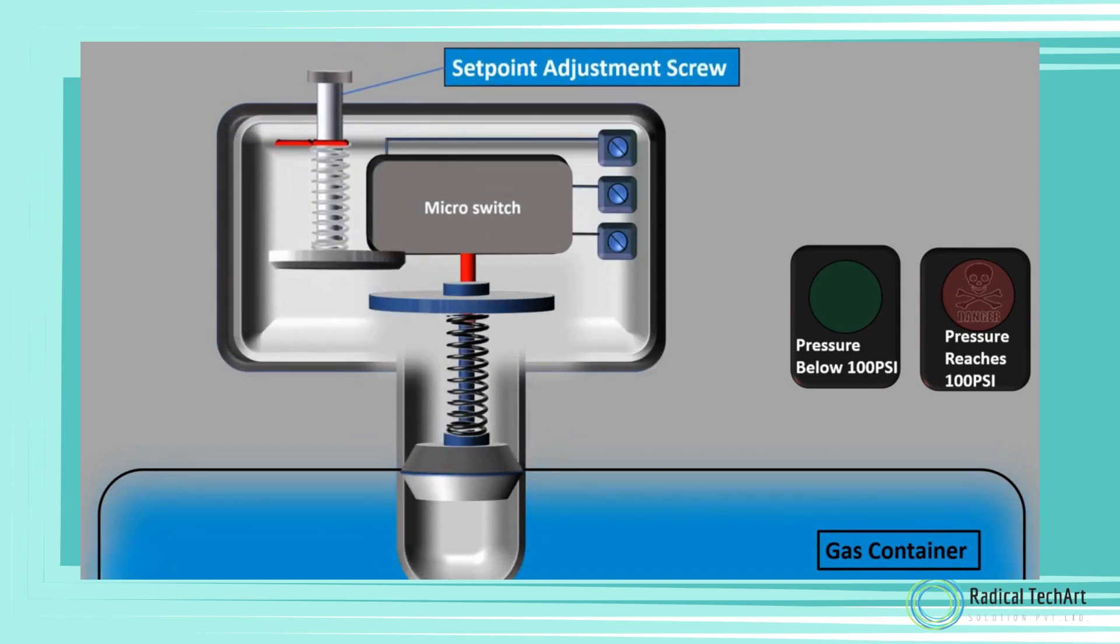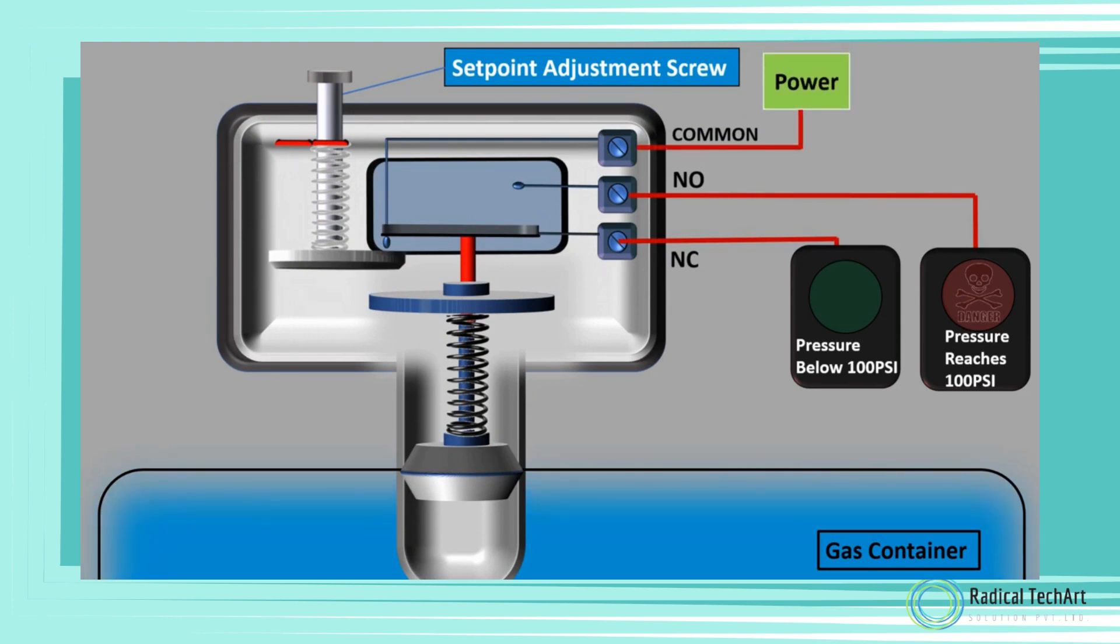Now we wire the green light to normally closed (NC) terminal of the switch and red light to the normally open (NO) terminal of the pressure switch. Power is connected to the common terminal of the switch.